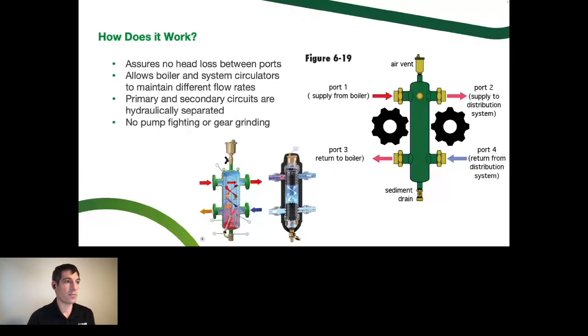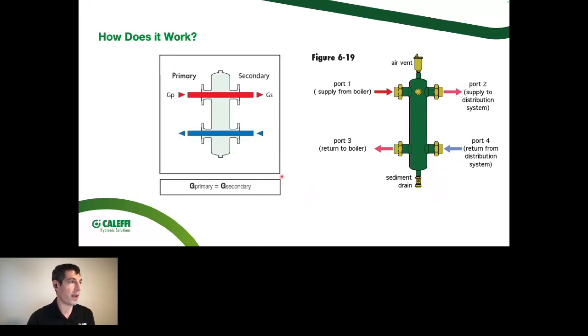There's not some sort of diversion that's happening with a motorized actuator or anything complicated like that. It's not mixing for a specific temperature. It's just a big wide spot in the river where those two flow rates can kind of bypass each other. So let's say that we are going to put in a hydro separator and somebody says, well, you don't need one of those. Does anybody have an example of where that could be true, that you wouldn't need primary-secondary piping at all, not any of the diversions, buffer tank, closely spaced tees, or a low loss header?